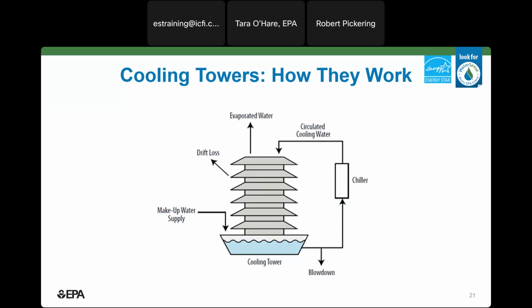So the cooling tower has a number of inputs and outputs that help explain how water is being consumed in the system. First, as I mentioned, there's this circulated cooling water loop that is introduced into the tower to be cooled. The water is removing heat from a piece of equipment and is then returned to, in this case, a chiller, and it is returned to the chiller once it's been cooled in the cooling tower. Some of this water is evaporated to remove heat.